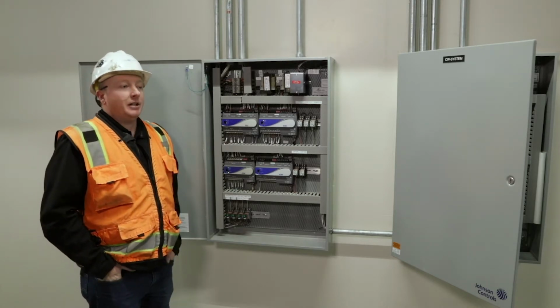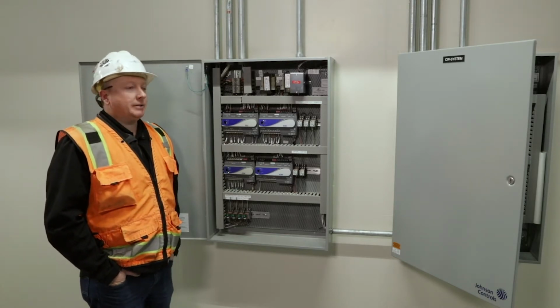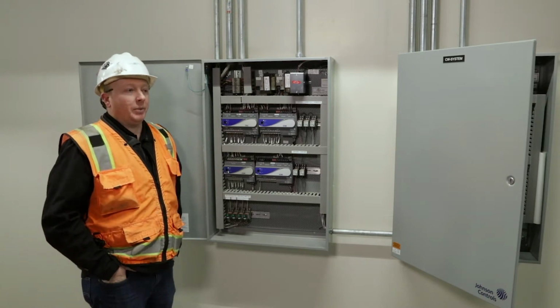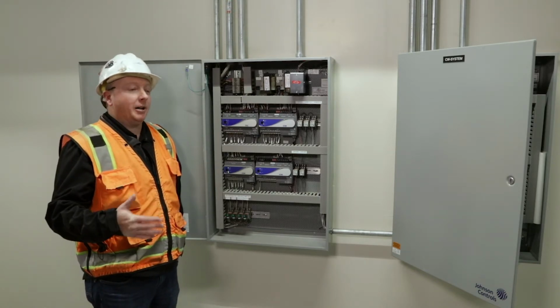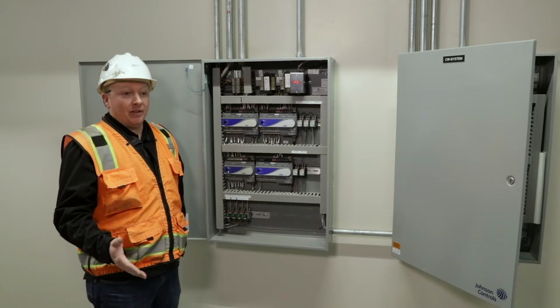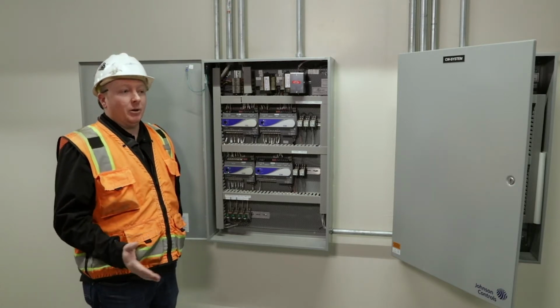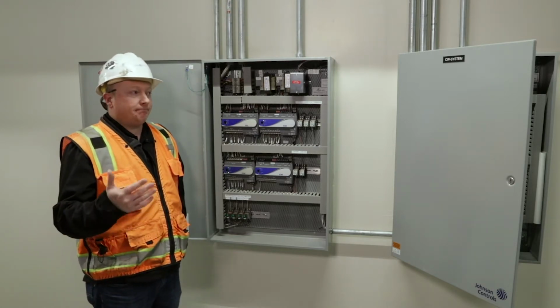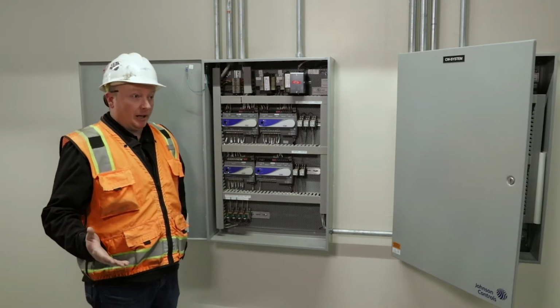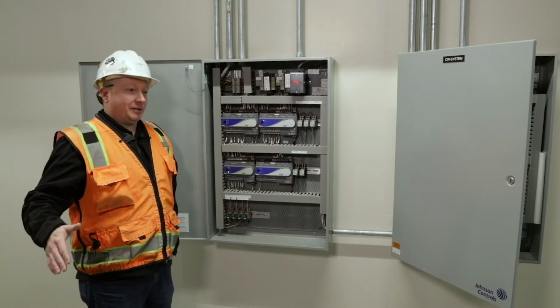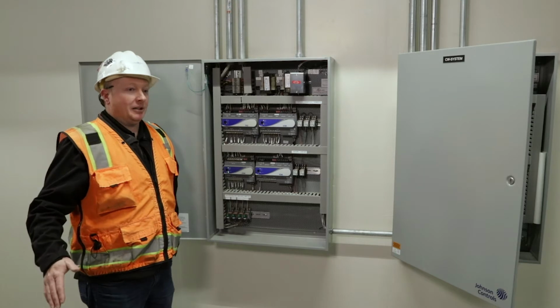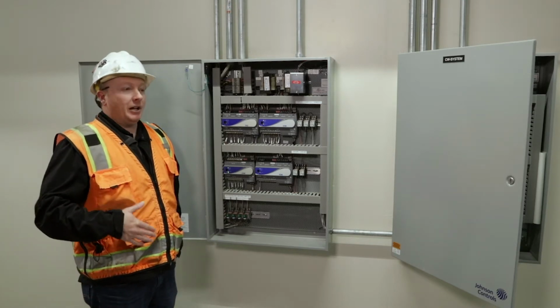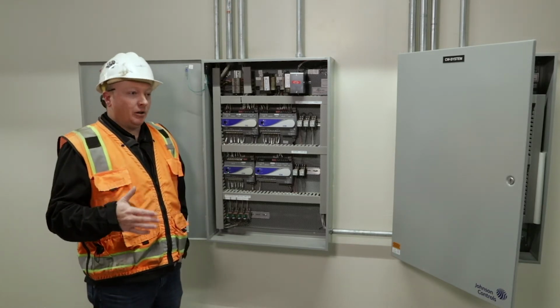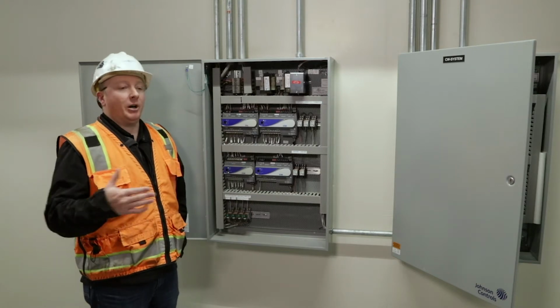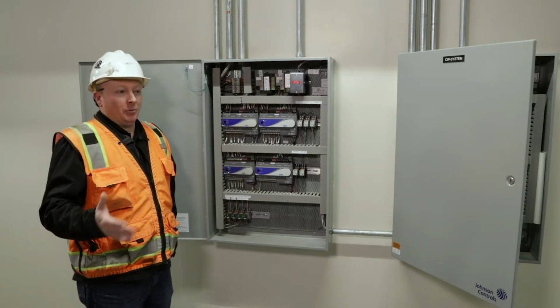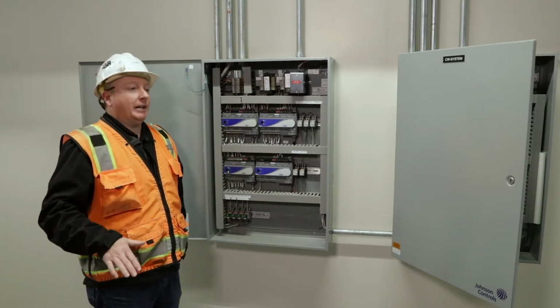The chillers stage based on load. So basically, well, let me back up. We start a chiller based on valve position of the air handler. So if any one chill water valve gets over 30%, that's when we turn the plant on. It picks a chiller with the lowest runtime, and it starts that one first. If that chiller gets above 95% load for X amount of minutes, we bring on a second chiller. That's really the basic staging of the plant.